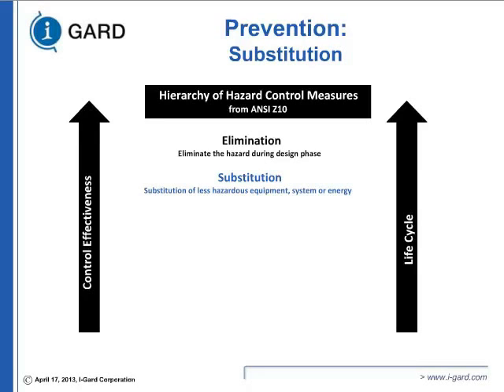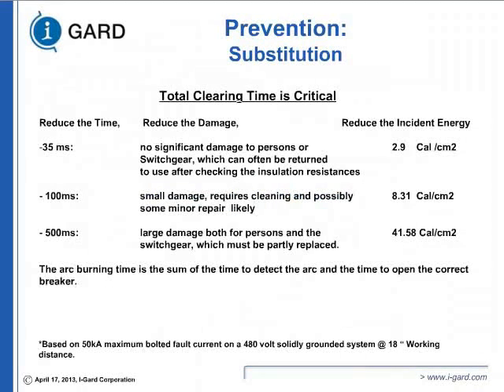Okay. The next item is substitution. What is the technology to substitute with a less hazardous or less risky environment condition? You will see a chart on your screen showing what happens by reduction of time. If you can clear the fault in 35 milliseconds, which is about 2 cycles, your incident energy based on a 40 kA fault at 18 inches working distance is about 2.9, as compared to if it clears in 100 milliseconds, which is roughly 6 cycles. You'll see it has gone up to 8.31.